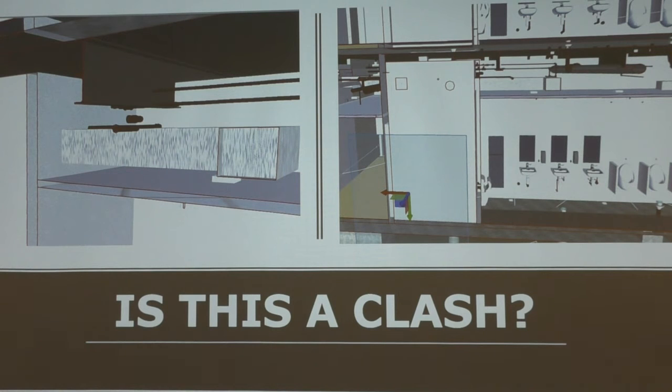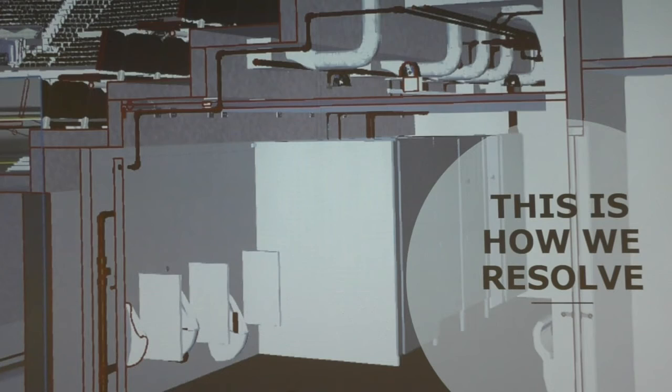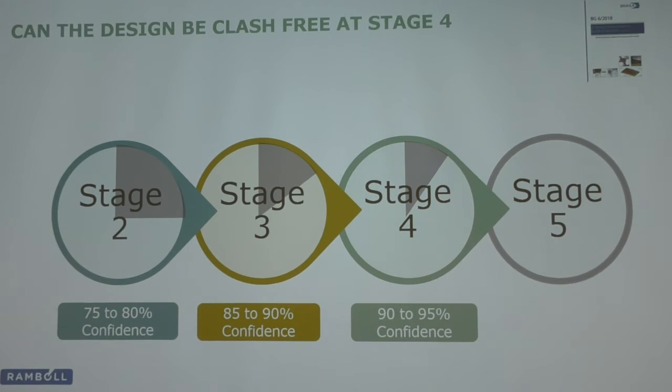So if it was feasible, we wouldn't have put inverts on those pipes. In a 2D world, you wouldn't. I mean, this is an example of what people then do to try and get rid of a clash, because this particular job had a clash, and then someone did something very stupid in the BIM model and just followed all the radiators. When actually, in a 2D world, you'd have drawn a line, put a dot on it, drawn the line down, put a dot to all the toilets at the back of it, and the plumber would have put a T and a 90 and made it work. So we're taking again in the 3D world some of that.